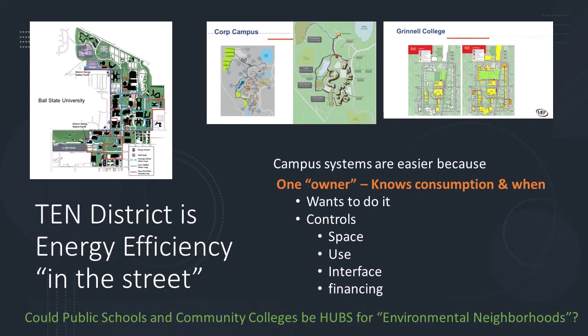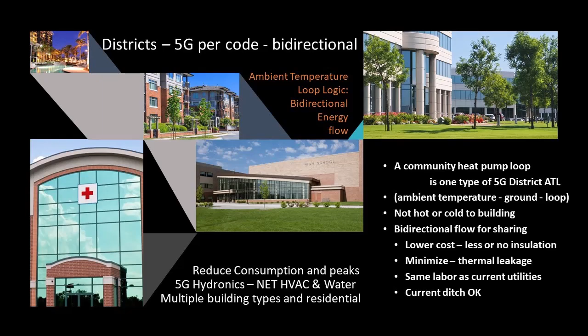The other part of it is it's bidirectional, so any DX cooling equipment works better. Any heat pump heating now isn't a matter of a COP of 2, meaning it costs half as much to heat this building than it would with 100% electricity. Now the COP is high enough—4, 5, 6 simultaneous—that it ends up costing less than gas.